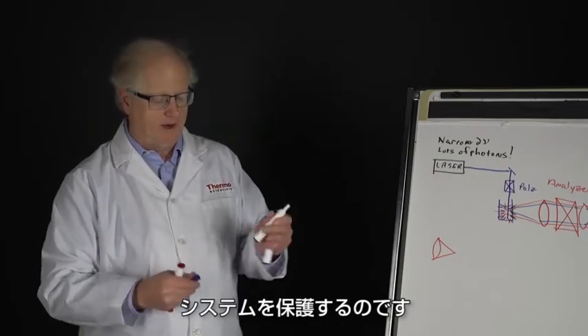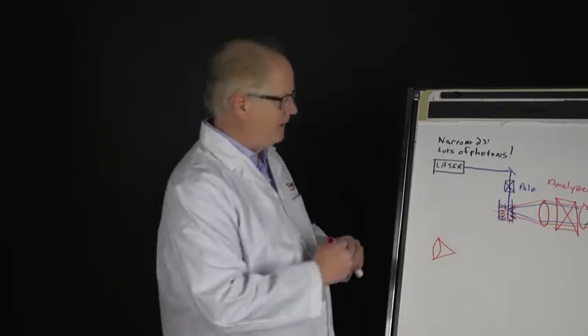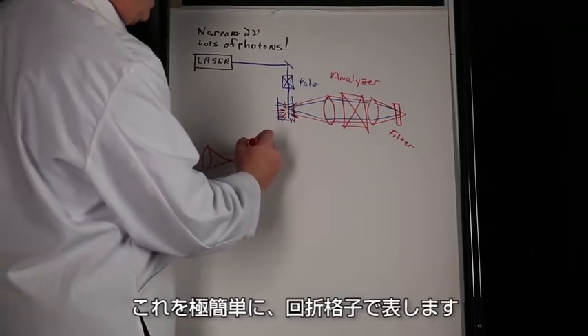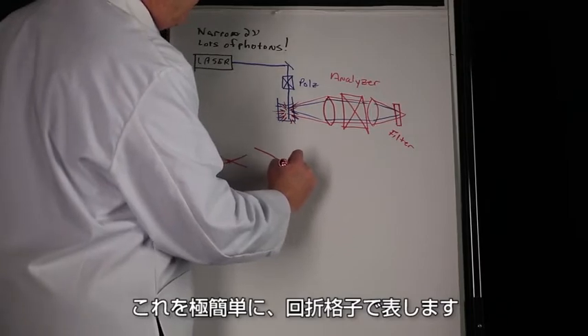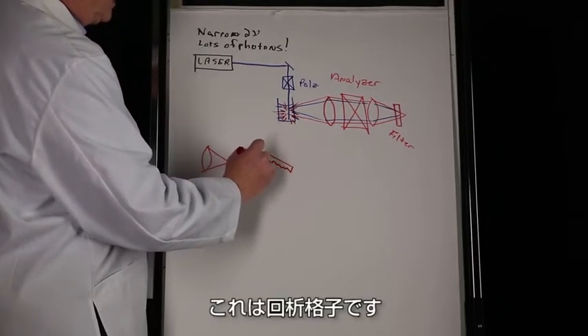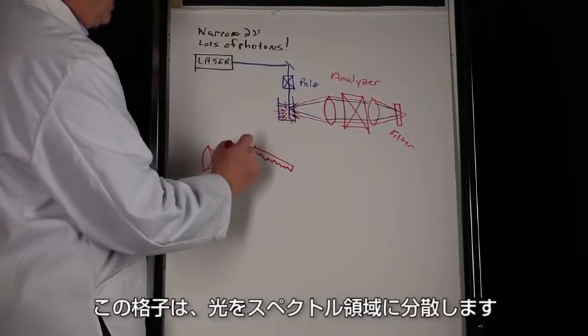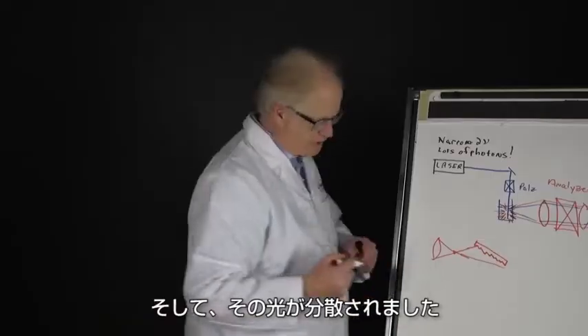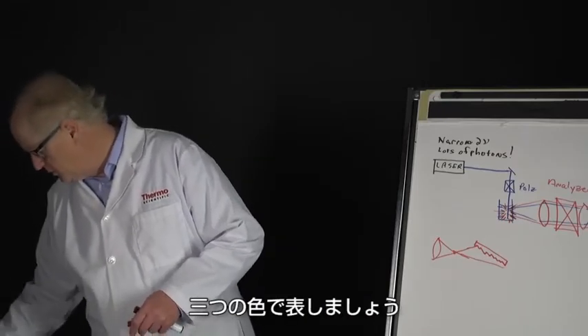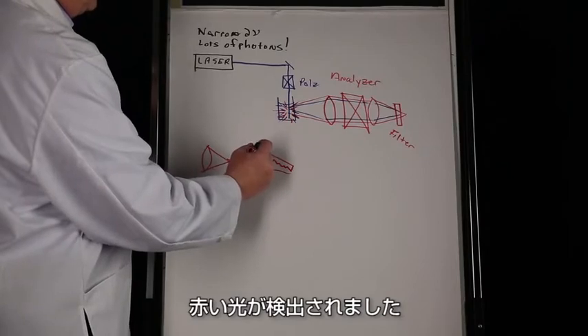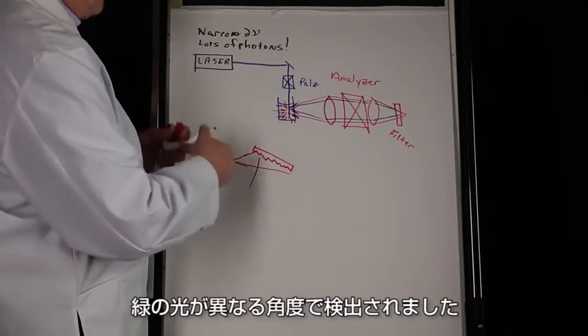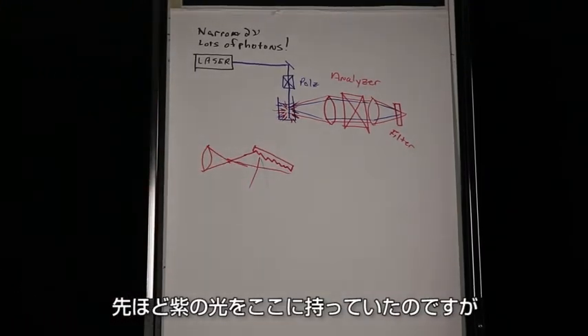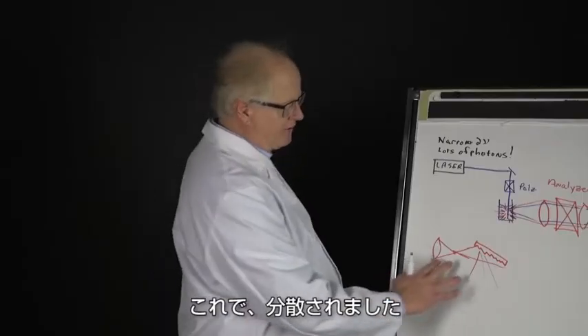The next thing is that light enters into some sort of diffraction element and I'm going to draw the simplest, which is going to be a grating. So this is a diffraction grating - it spreads the light out over its spectral range. So now you have the light all coming together, now you have it spreading out. So I have the red coming out, I have the green coming out at a different angle, and I have my violet light coming at a different angle. So now I've spread them out.